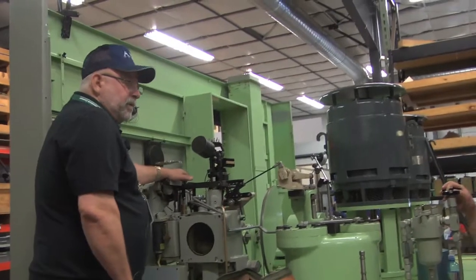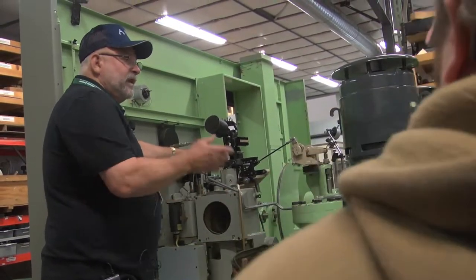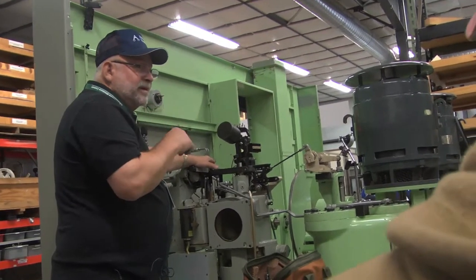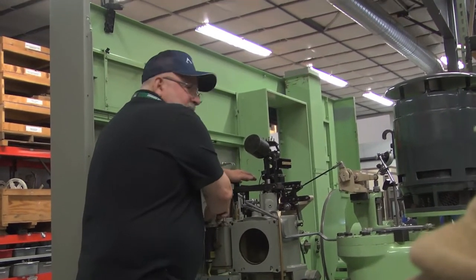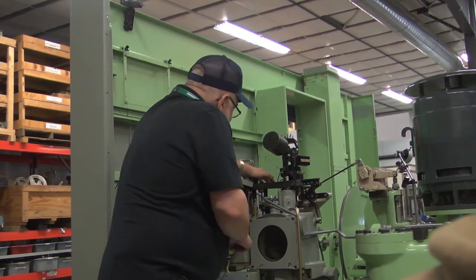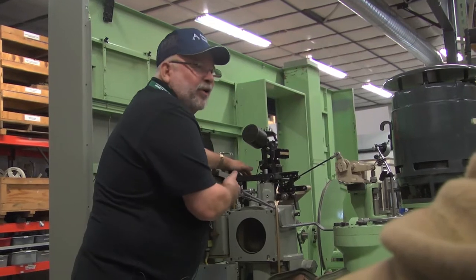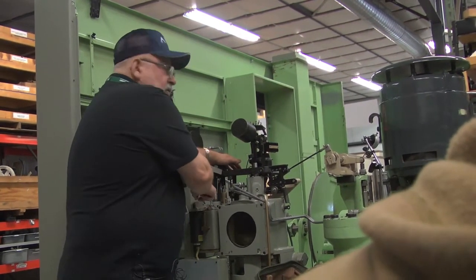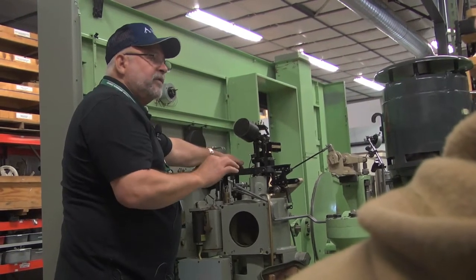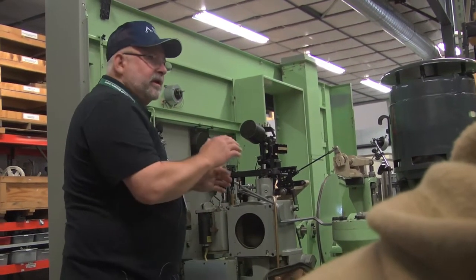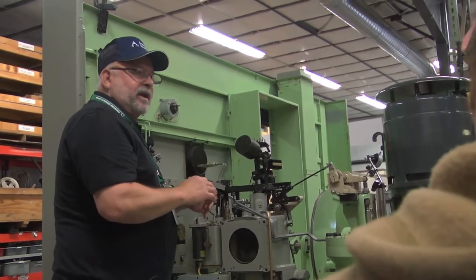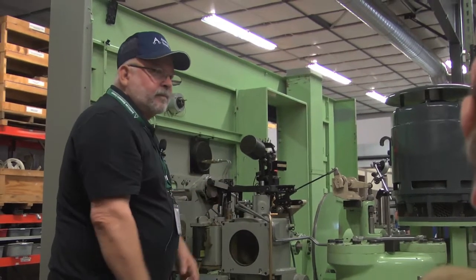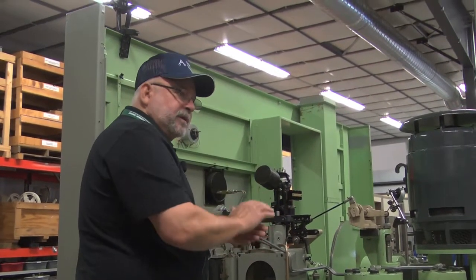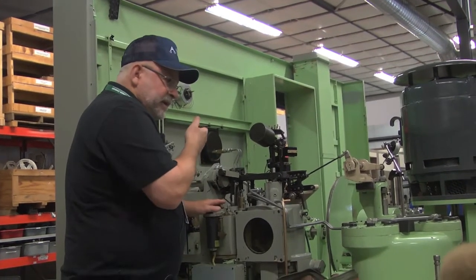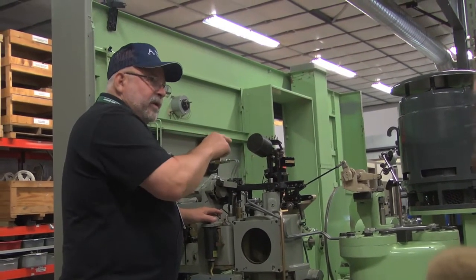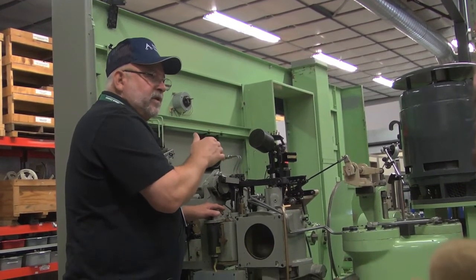Have you guys ever had a problem with hunting on your Pelton units after you've taken the dash pot off and refilled it? You have to sit here and hold this bypass down, and when not on line, I'm moving it all over right now, and you have to push hard and keep this open and just keep doing that till you get that air out of there. It will not function at all. It'll be one of those hunts where you say, oh good, I've got it, and then all of a sudden it'll hunt. Yeah, it's not constant. I think on a Pelton that little bit of air on the other side finally makes its way over there, and that bubble gets up there and it hunts for a second, and then it'll straighten itself out.